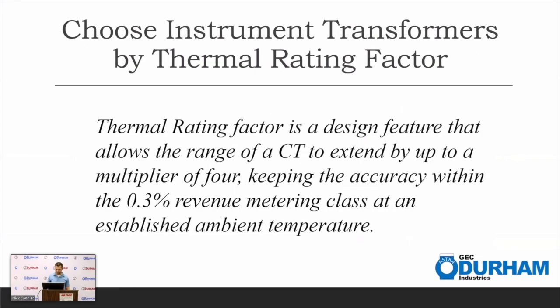Gotcha. So back to thermal rating factor. This is a feature of CTs that allows you to extend the range of that CT by up to a meter multiplier of 4, all within your accuracy class. In this case, 0.3 accurate for standard and extended range transformers.